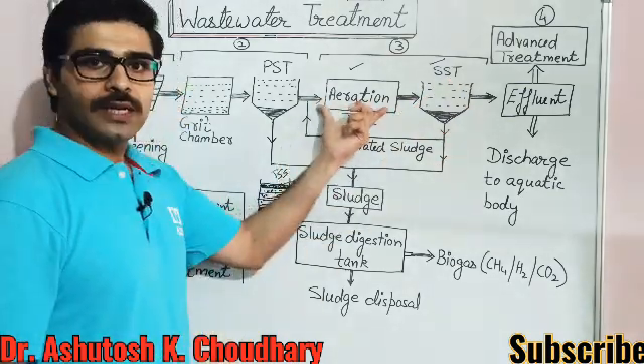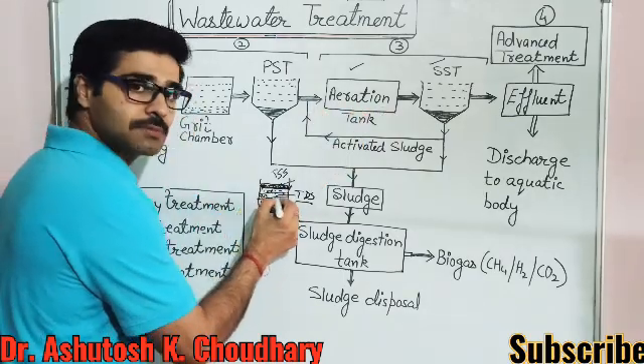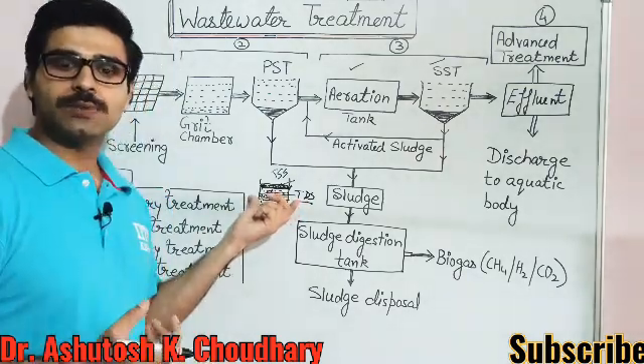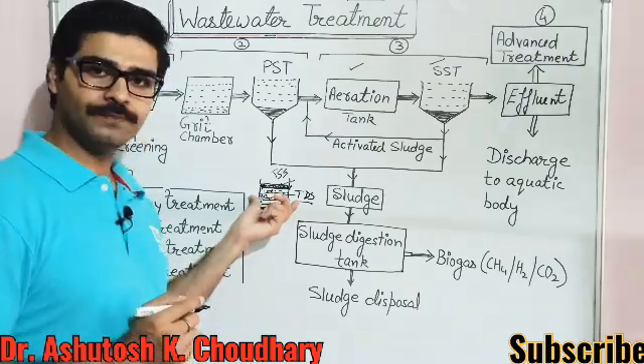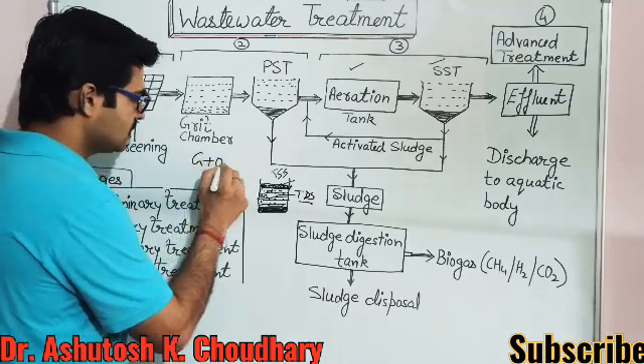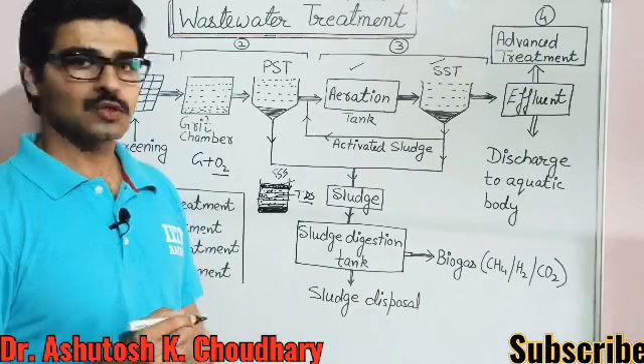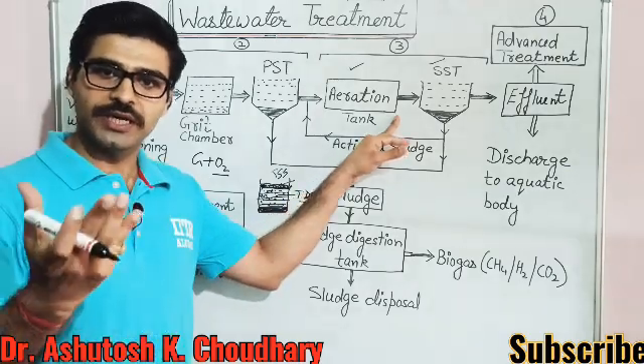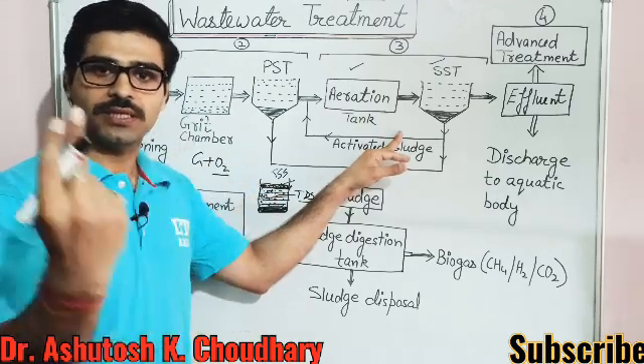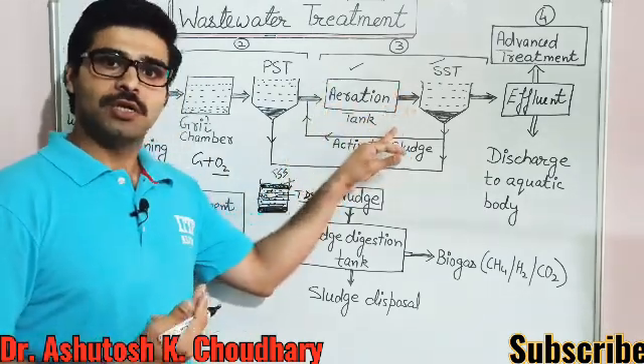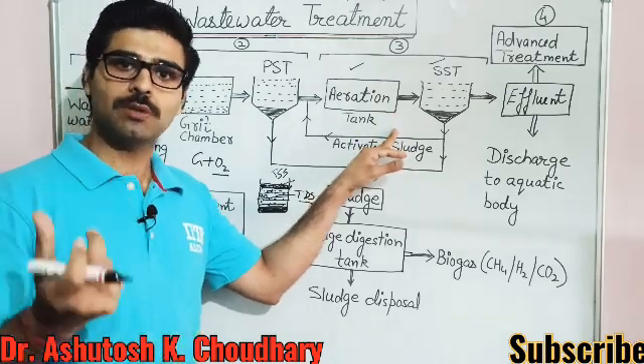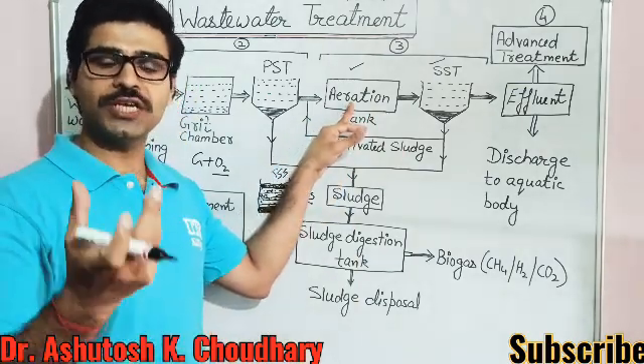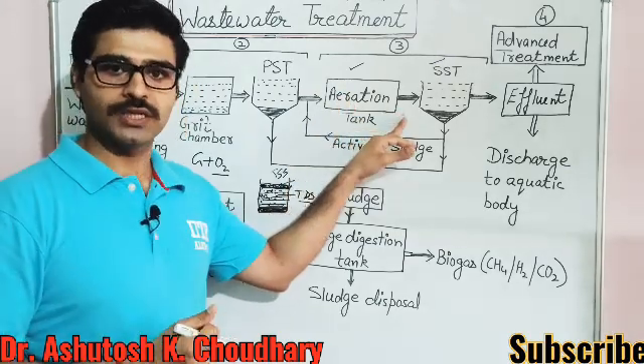In the aeration stage, whatever organic matter is present — for example carbohydrates and fats — bacteria will oxidize it. To oxidize glucose, for example, oxygen is required. So in this stage we aerate the wastewater using pumps and aerators that continuously aerate and agitate the water so that oxygen dissolves well into the water, enabling bacteria to oxidize the organic matter.